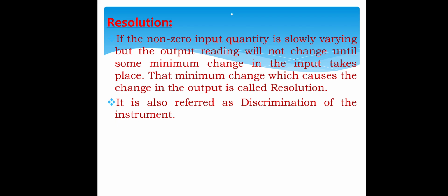Next, resolution. If a non-zero input quantity is slowly varying, the output reading will not change until some minimum change in the input takes place. That minimum change in the input which causes a change in the output is called resolution. It is also referred to as the discrimination of the instrument. So I am giving input but there is no change in output until the minimum change in the input takes place.